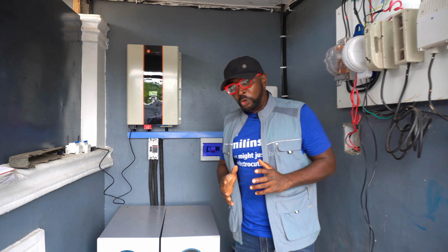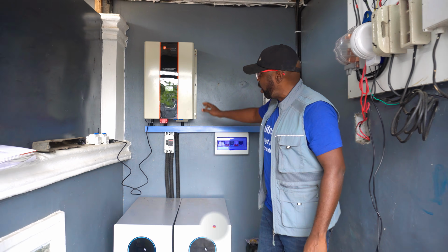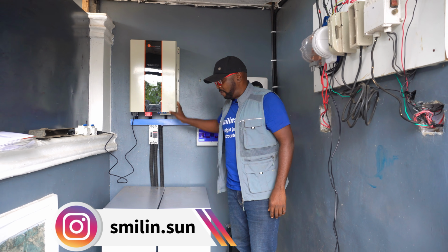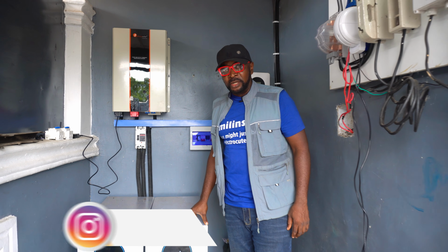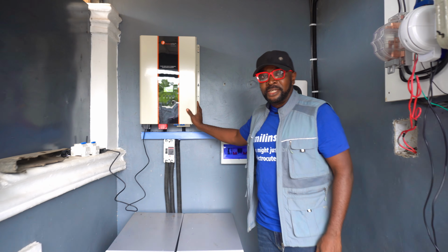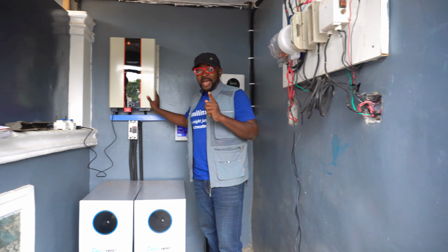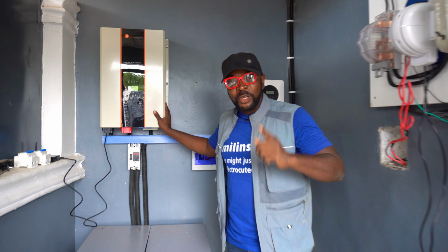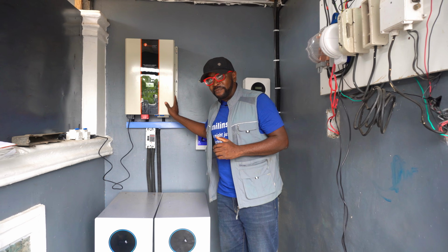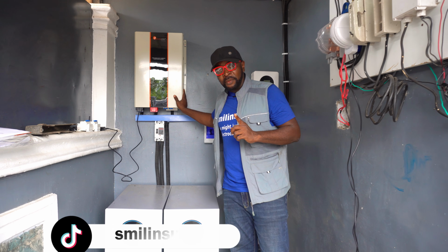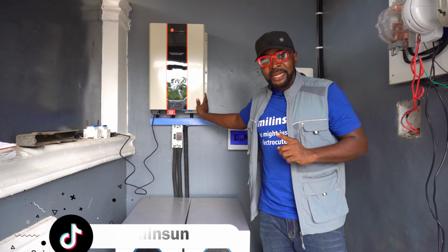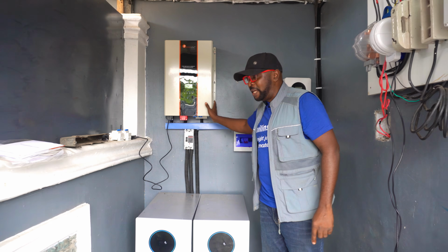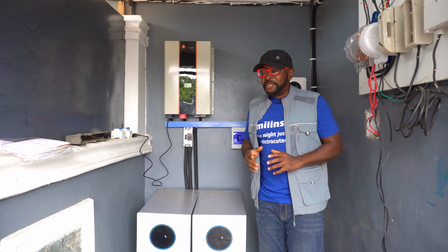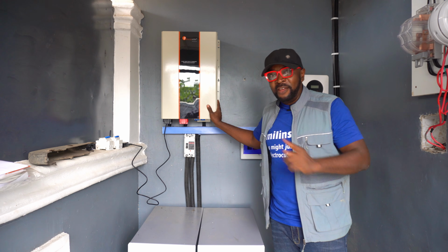One of the good benefits we'll get from taking off this inverter is that the system will be more energy efficient, because this particular system has one problem: the fan never stops. The fan of the inverter is not supposed to be on at all times. Its purpose is to regulate the temperature of the inverter, but we've noticed that with this particular inverter, the fan never goes off.